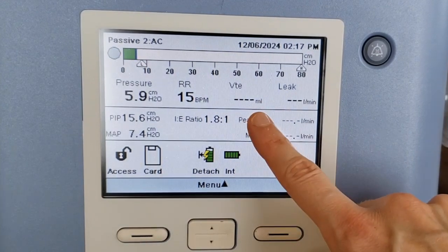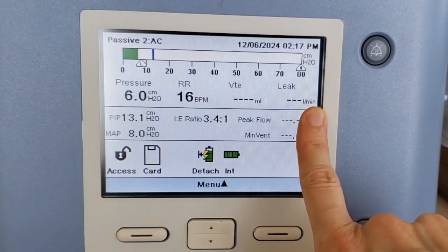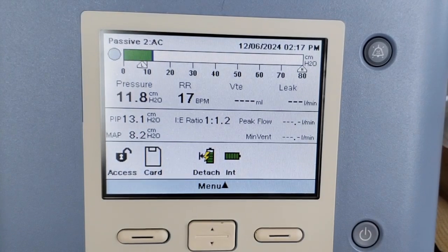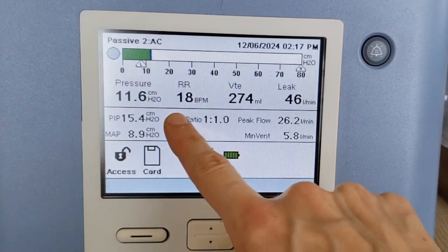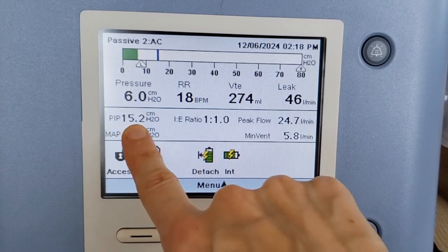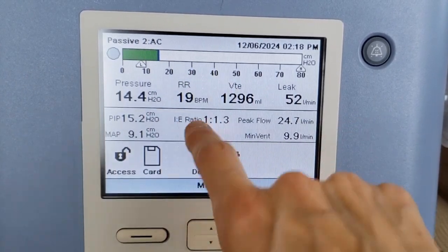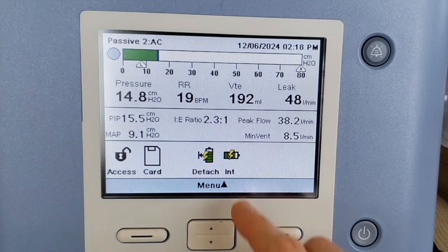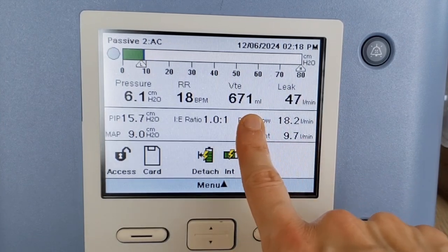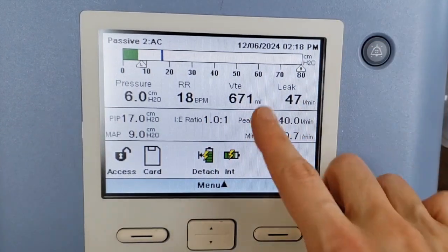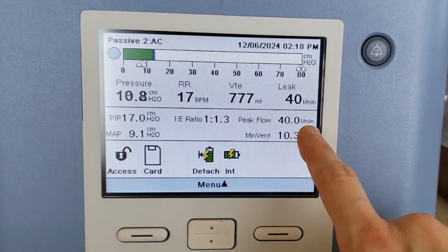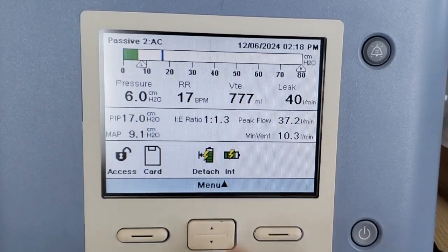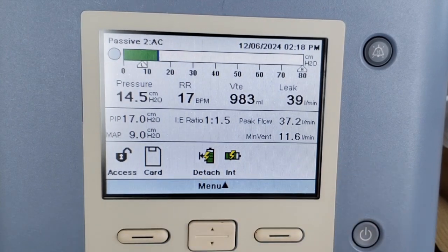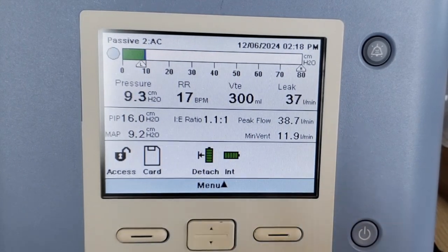And as you can see, I switched over now. And so now these numbers are going to actually register. Just got to wait for them to come up here. You can see my pressures are now higher. I'm now at about 15.2. Respirations are a little bit higher because I'm getting out of breath because I'm talking. And then the volume total exhaled is going to go up here. It's going to go to about 650, which is about where I usually sit. And the leak now is down to 40. So there are a couple other numbers on here, but it's nothing that concerns me.